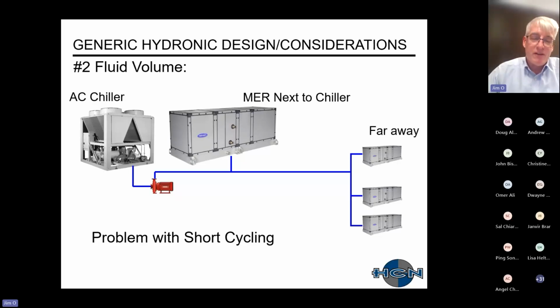So this is just a schematic showing a problem that I ended up witnessing on a job that I sold, where we ended up with a problem with short cycling. I don't remember the exact tonnages, but basically we were working at a museum and they were replacing their chilled water systems. We put an approximate 100-ton air-cooled chiller out on a roof. We had a very large air handling unit serving multiple galleries right next to it. And then far away, maybe 100, 150 feet, we had small 5, 10 or 20-ton indoor air handling units. So if you took the calculation, my chiller of 100 tons, and included all the piping to those faraway units, I met my requirement of 3 gallons per ton.